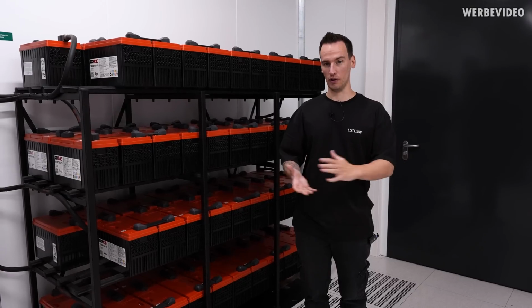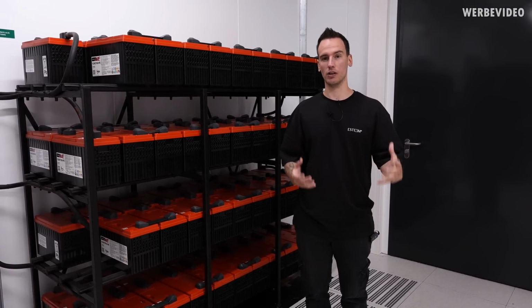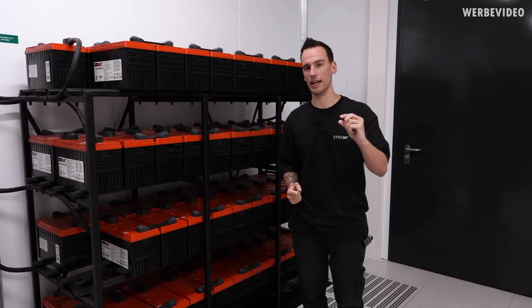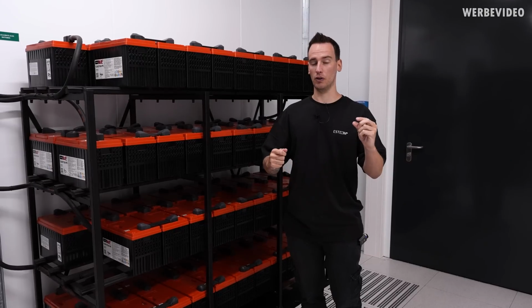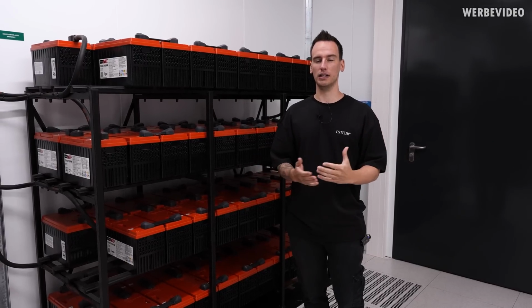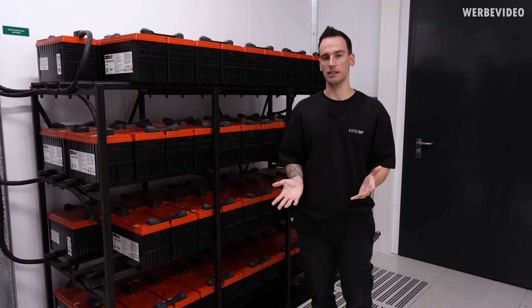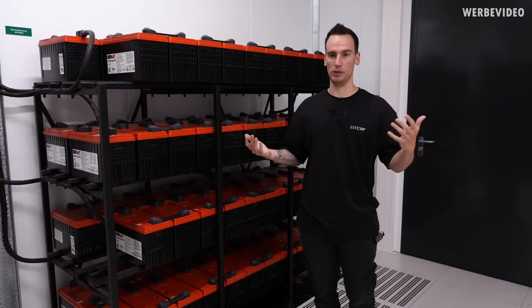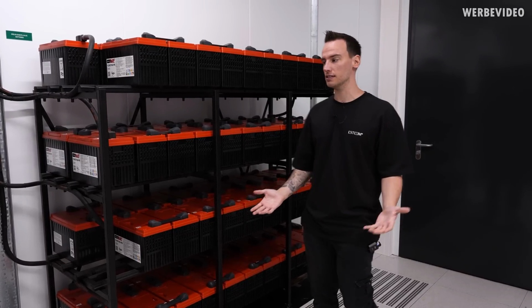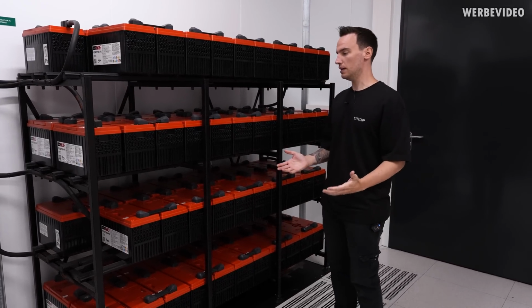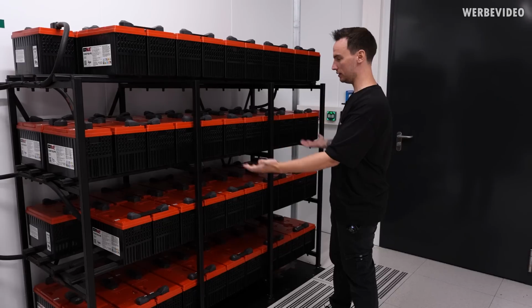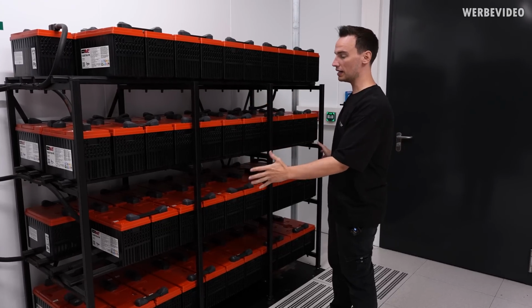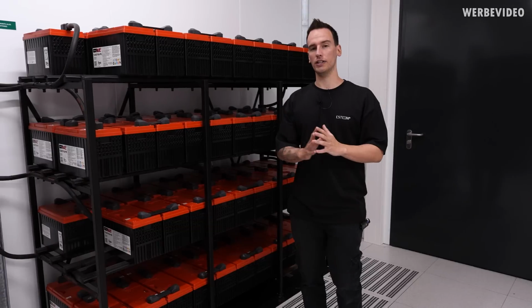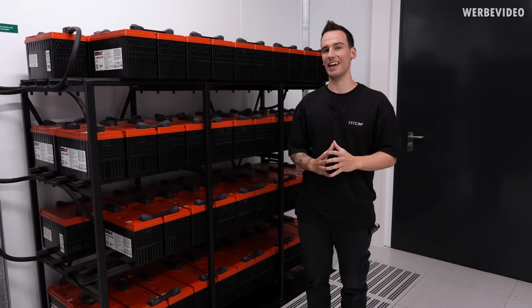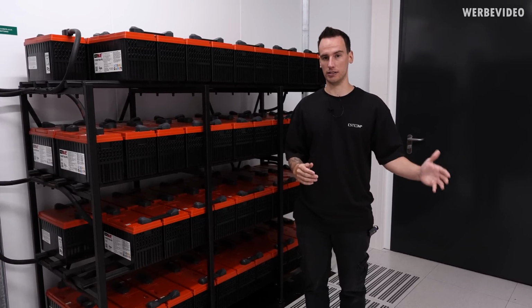In case power fails and the generators are required to start, there's a small gap before they reach full power, typically between 30 and 60 seconds. To make sure power isn't out during that gap, we have the UPS. Part of the UPS are the batteries, and we have one stack right here. The entire data center, running at full load, can run about 20 minutes just on batteries.